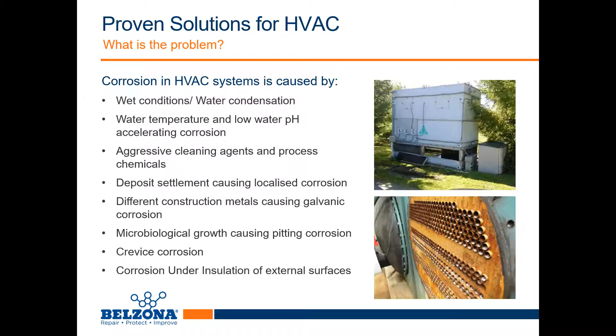Galvanic corrosion. Usually there are two different types of metals in these systems. And as we know, the two different types of metals are connected. With exposed moisture or water, corrosion can occur. Microbial CUI as well. Other problems in HVAC systems include your cooling tower fans. Cooling tower fan blades usually suffer from erosion on the leading edge, as well as cracks and flaking on the edges, reducing the overall efficiency of the cooling system, ultimately leading to failure.